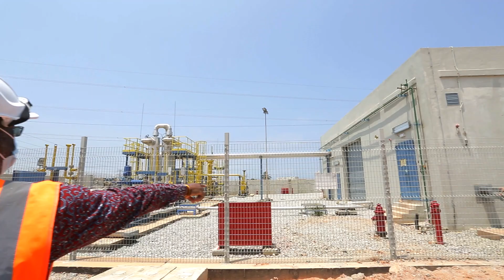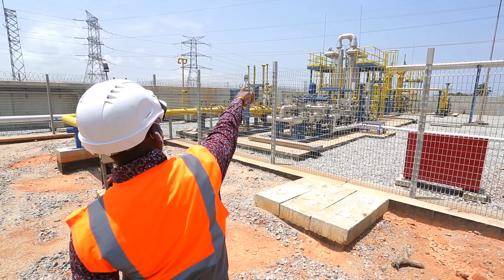Additionally, as the gas goes through, the boilers heat it, and it comes through those two heat exchangers. The heat exchangers bring it through the regulatory metering, which delivers constant pressure from this pump right on to the gas turbines. The filtering station, the gas exchangers, and the regulatory meters have redundant equipment so that we don't have a single point of failure - we're still able to work.